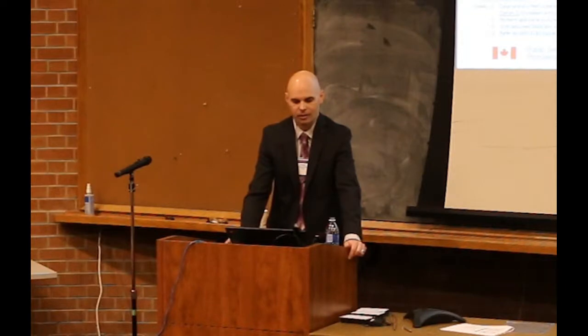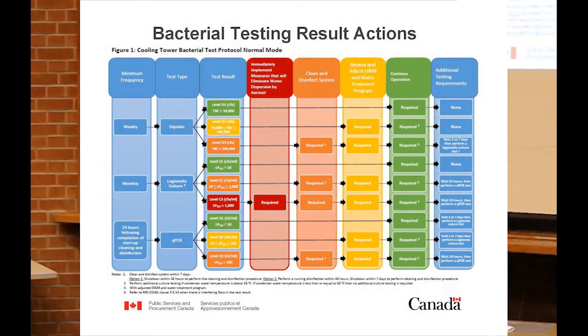Appendix D of the standard for each of the different main system types has those different maintenance action levels that need to be employed, and then the follow-up maintenance actions that need to follow. So if you're at a red level, the initial maintenance action is to immediately stop operation of that equipment and remove aerosol exposure. So if we're talking cooling towers, it's shutting down the fans on the tower or shutting down the tower itself.